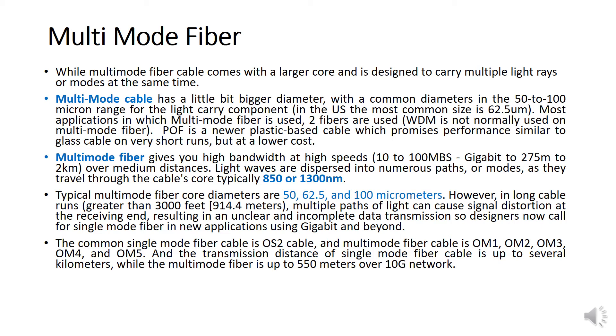Based on my experience, we use subsea cable that runs around 20 to 25 kilometers depending on the project, along with what we call composite cable. Multi-mode fiber can be used up to 550 meters over 10 Gigabit networks. The rule of thumb is: panel to panel, server to server, or cabinet to cabinet — same room or next building — as long as you're within 550 meters, multi-mode fiber is fine.